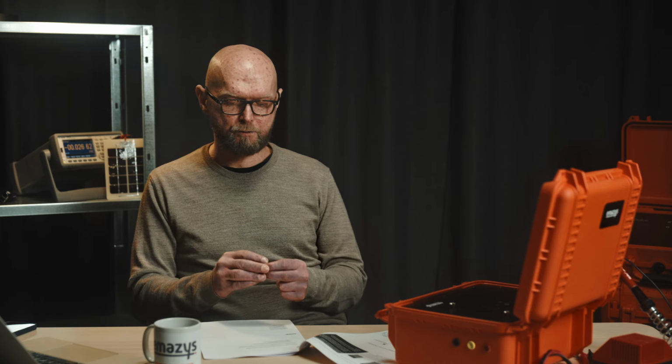But the most important one, I would say, when you're going to a new PV system, you don't know what is wrong, you just know that it's not producing the power it should. I would be immediately suspicious about the DC distribution faults in the cables and the connectors. Make sure it's not that. And then thing number 2, what about grounding? What about isolation faults? That's the second part.